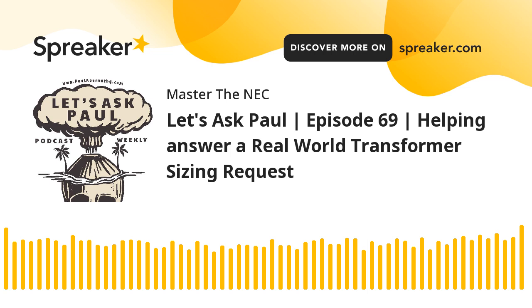Now that's disconnecting means, and that's specifically for the transformer. It says, transformers other than Class 2 or Class 3 transformers shall have a disconnecting means located either in sight of the transformer, which is what you want to do. You want to put one right beside it, or in a remote location. Well, I'm saying this remote location could be back at your 480 volt panel. It says, or in a remote location, and that is remote from where the transformer is at.